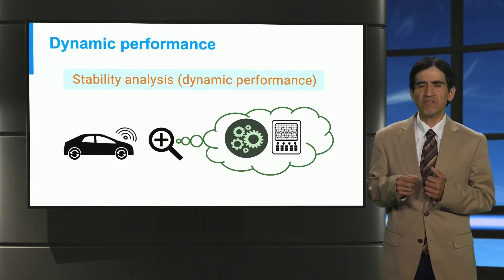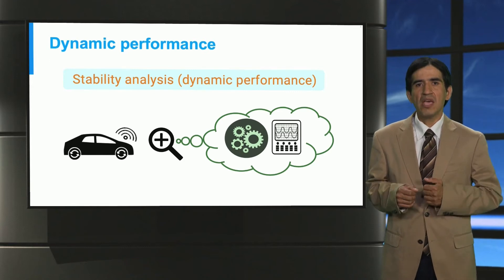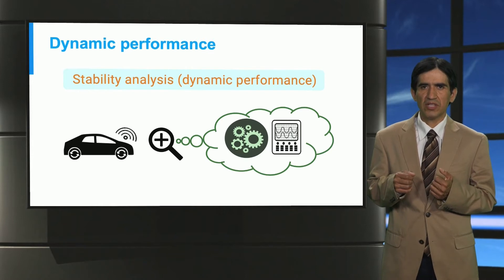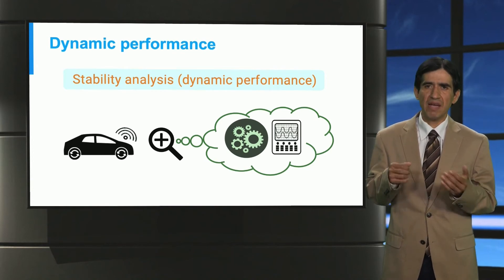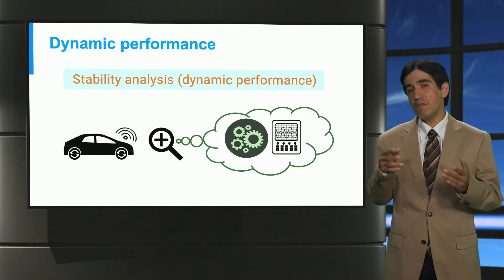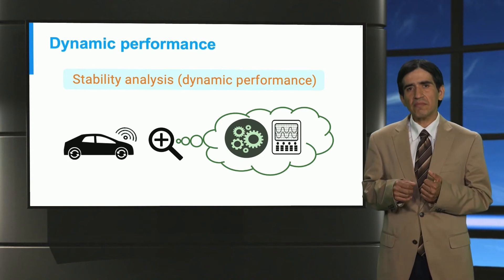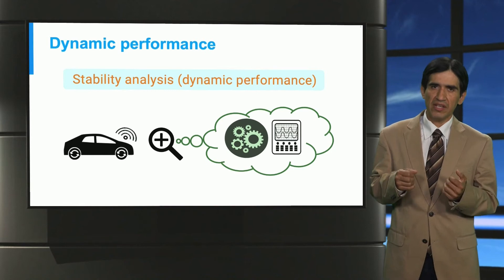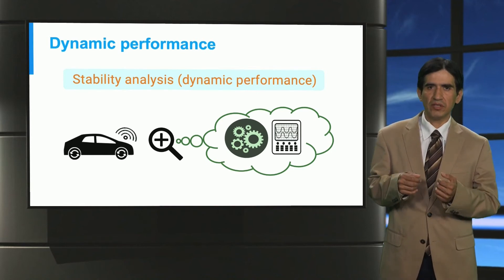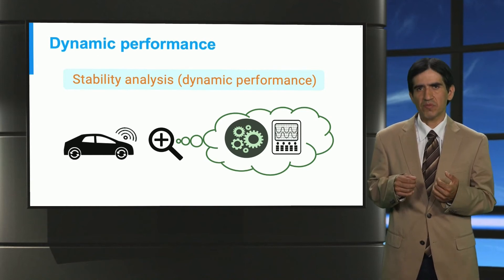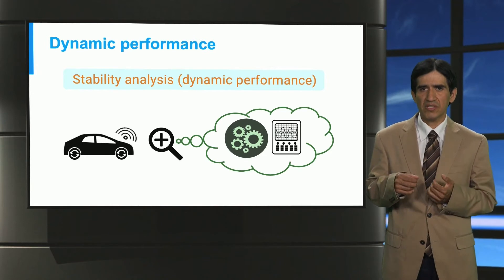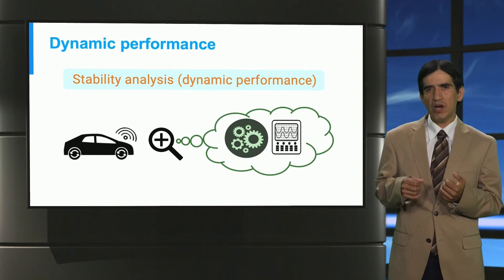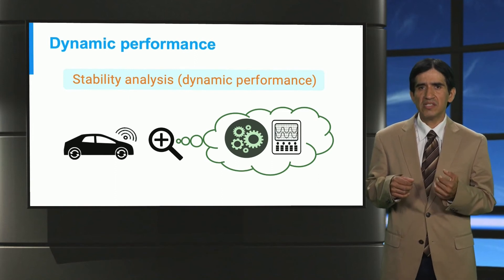Let's look at an example in terms of a measured response — for instance, the voltage magnitude. If we solve the power flow calculation, we get a value for the voltage at a certain bus. If the demand and generation do not change with time, you will get a flat response from solving your dynamic models. This means that we are operating around a stable equilibrium point. But if a disturbance happens — it could be a short circuit or a generator outage — then the solution of your differential algebraic equations based model would not be a flat line, but actually a dynamic response. If the system returns to the same operating point after this behavior, then the system is said to be stable. If something happens, such as a topology change, the end operating point might be different than the original one. However, as long as the new operating point is close to the original point, the system can still be called stable.